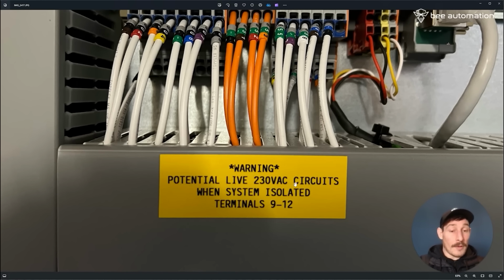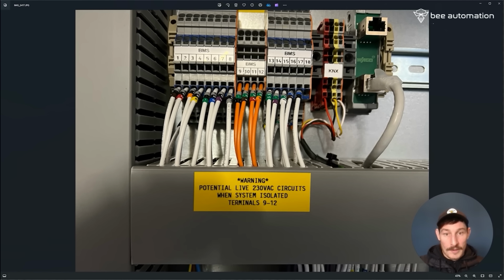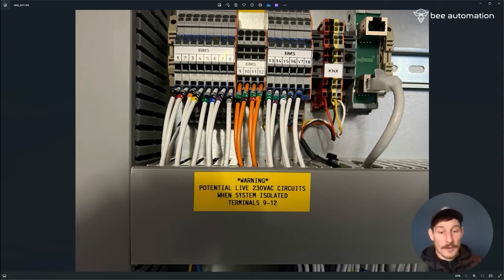The label reads: warning, potential live 230 volt AC circuits when system isolated, terminals 9 to 12. I put this on the trunking because it's very clear, but trunking can get lost over time or not put back in the right place, so I've also added a smaller label here. Bear in mind this area is probably going to be covered up with outgoing cables once it's commissioned, so people won't necessarily see it as easily - that's why I've put two labels there.